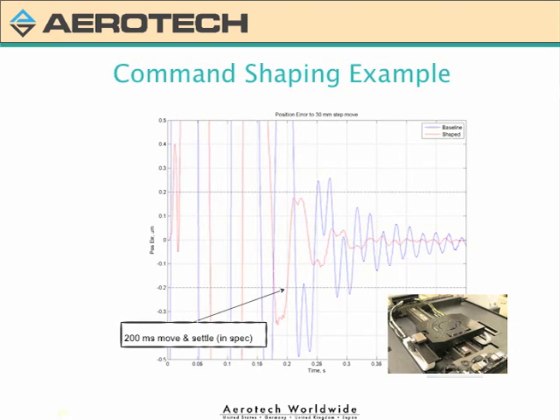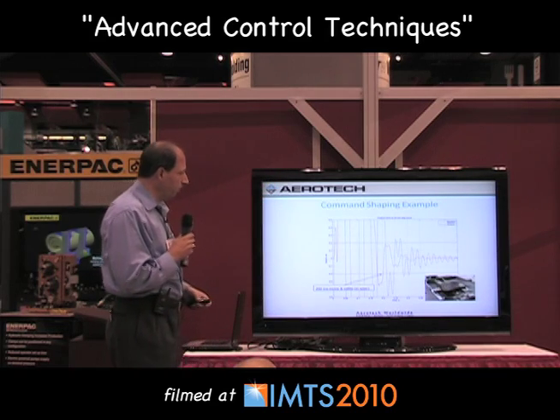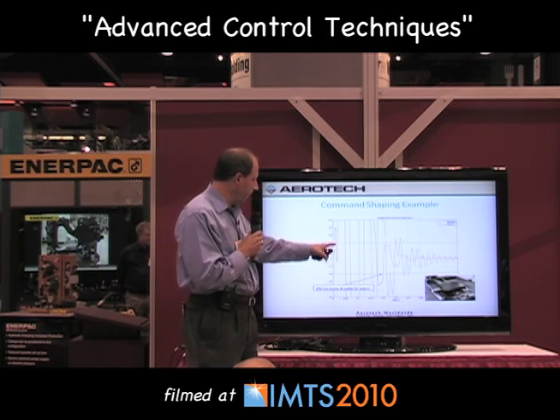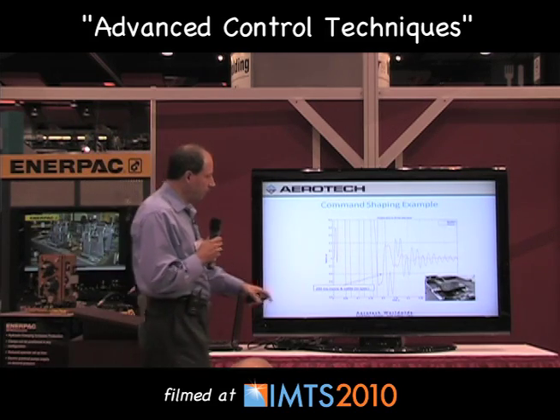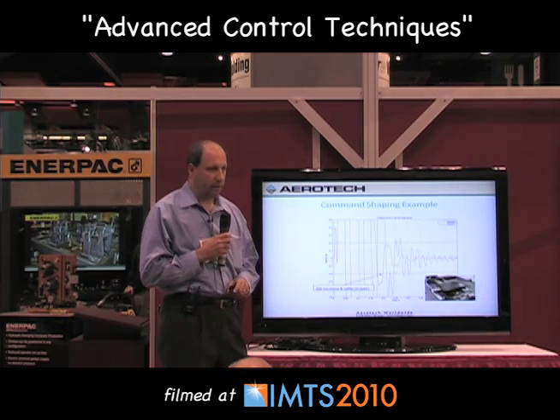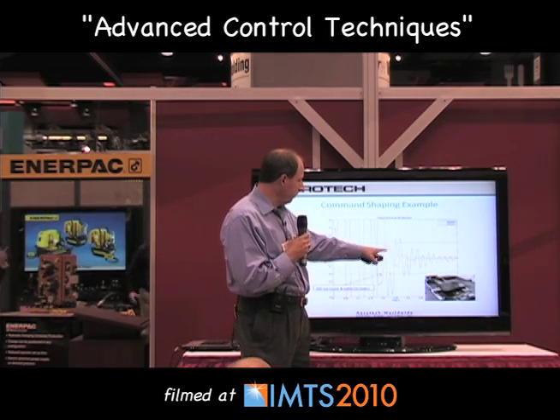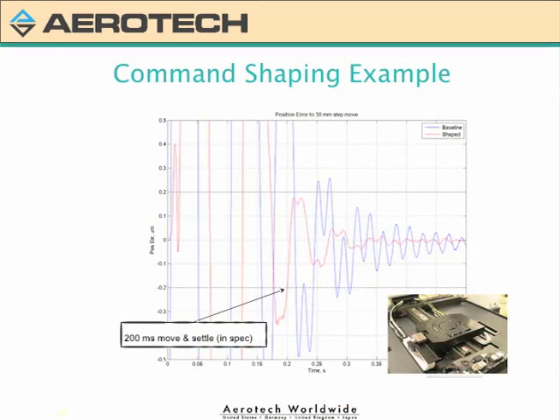Here's a simple example of that. I'm only looking at the end of the move, not the move itself. You can see in the blue line the end of the move, and I'd like to settle within plus or minus 0.2 microns. Without the command shaping filter, it takes until about somewhere well into the transient to settle. I then apply the command shaping filter, shown in the red line, and I settle much sooner. I've seen 15 to 30 percent improvement in settle time using this technique.